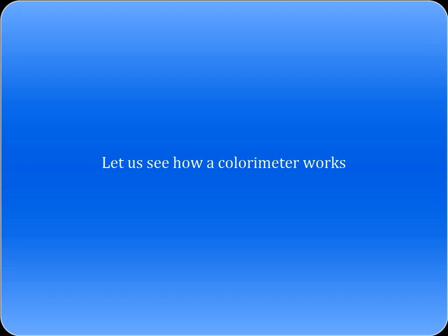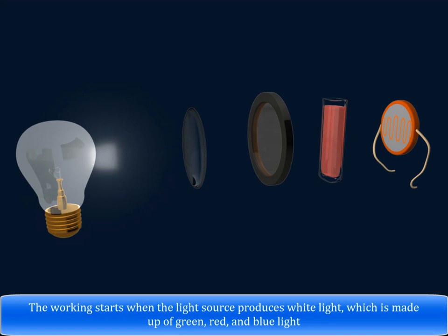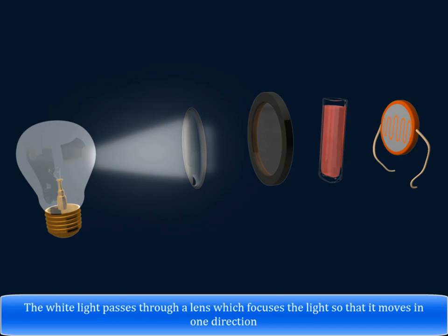Let's see how a colorimeter works. The working starts when the light source produces white light, which is made up of green, red, and blue light. The white light passes through a lens, which focuses the light so that it moves in one direction.